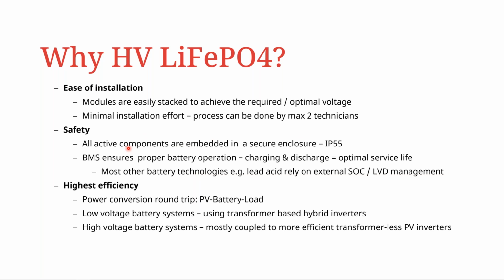Safety. All active components are embedded in a secure enclosure, which is IP rated 55. The BMS, or battery management system, ensures proper battery operation, so charging and discharging, and this allows for an optimal service life. Whereas most other battery technologies, for example lead acid, rely on external SOC (state of charge) or LVD management.